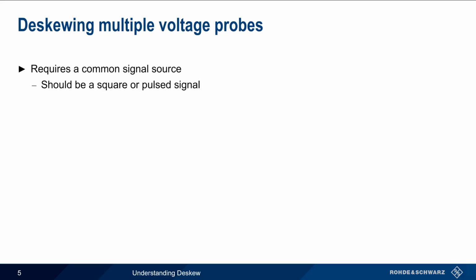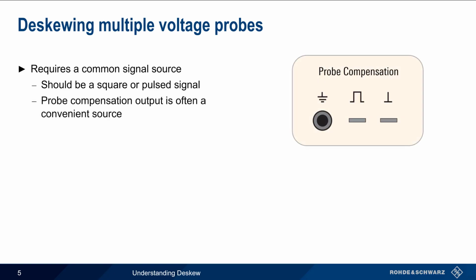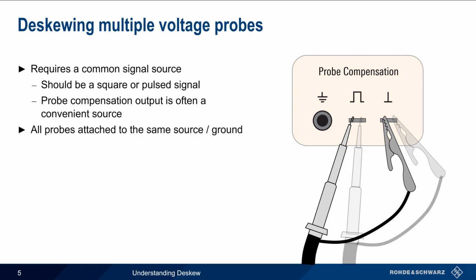Let's look at how multiple voltage probes are de-skewed. This requires a common signal source, and for ease of de-skewing, a square or pulse signal is recommended. The probe compensation output found on most oscilloscopes is a convenient source for this type of signal. The voltage probes are then attached to this source and to ground, and the waveforms for each channel are observed.